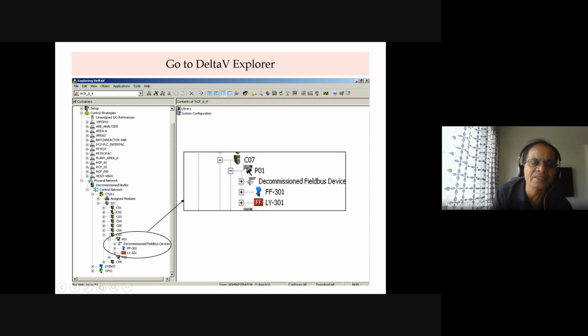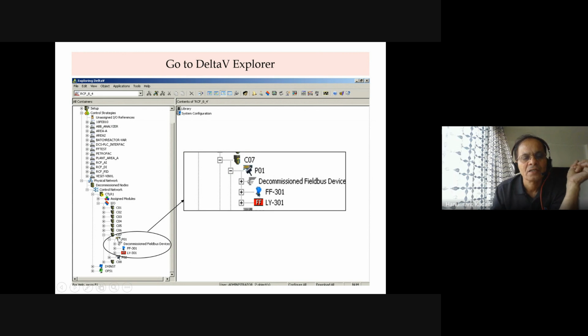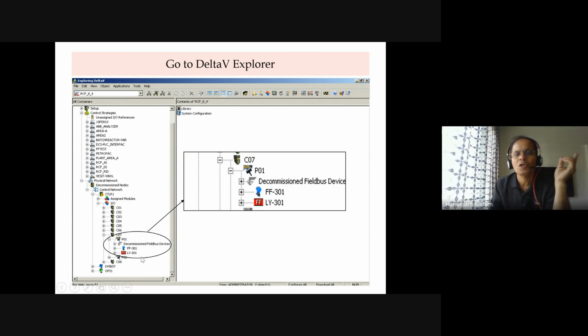There are 8 cards, 7 are shown here, and on card 7 you can see two assigned devices, FF301 tag and LY301, meaning two devices are there. Card 7 has two ports; on port 1 you have connected these devices. So card 7 is a Foundation Fieldbus interface card, and on port 1 you can connect these two devices directly.